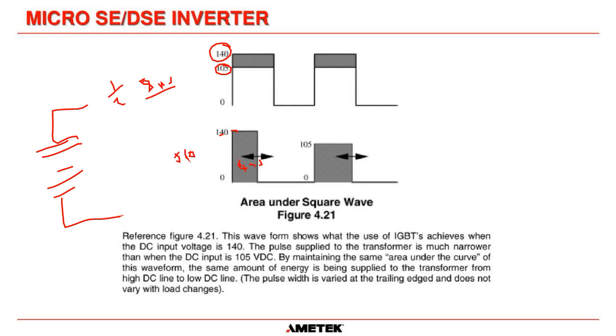If the battery just starts discharging and gets down to 105 volts, to get the same power out we need the same area underneath the curve — it needs to be 560. So you divide 560 by 105, and that means the pulse would have to be around 5.3 milliseconds.